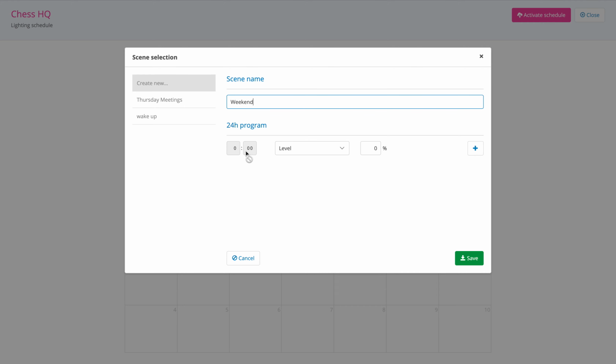So every day starts at 12 o'clock. And you can see here all the different control options. So level means that you can set a certain light intensity. Automatic means that you're giving control back to the building and to the sensors within that building. And 4 levels was specifically designed for horticulture. And unless you have very professional specific lighting, I do not recommend you use it.